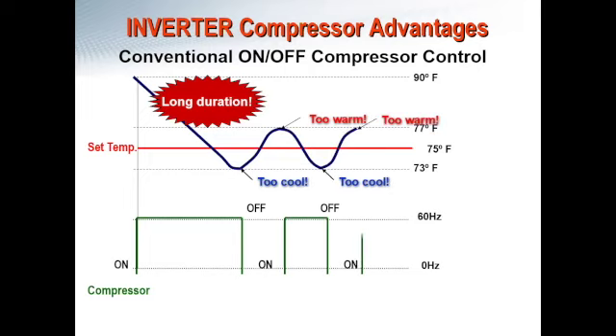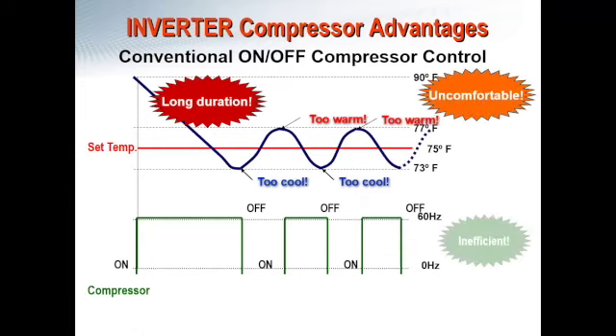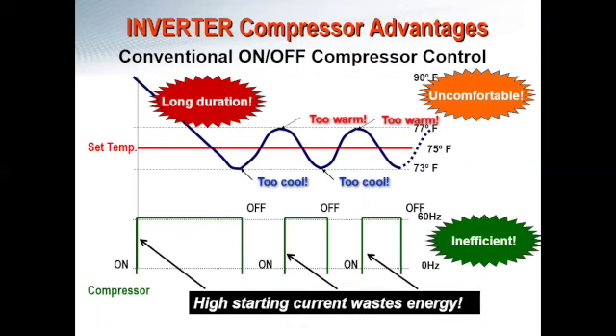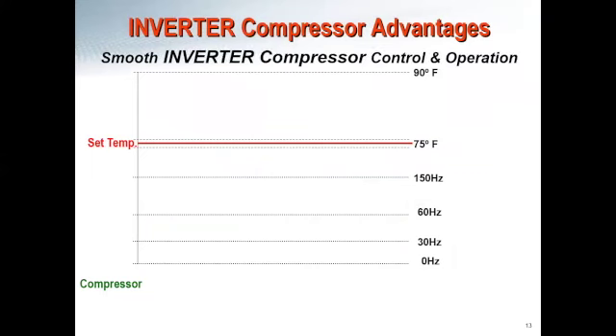This cycle is going to repeat itself, and I'm sure you've dealt with what we call hunting. It's basically the space between those two deadbands that the system is allowing the temperature to fluctuate before kicking on or turning off the compressor. This is a horribly inefficient way of doing things. Some mainstream or rooftop unit HVAC systems have moved towards a more modulated control, but we don't see it very often. And that's actually the exact kind of control that Mitsubishi VRF is going to use.